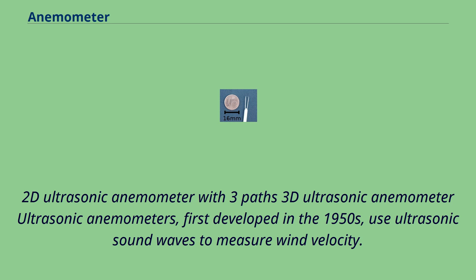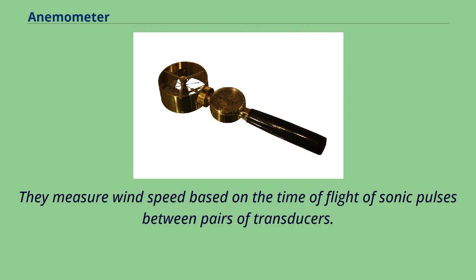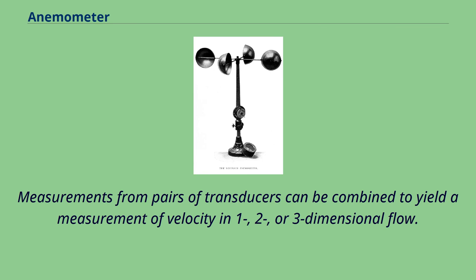2D ultrasonic anemometer with three paths. 3D ultrasonic anemometer. Ultrasonic anemometers, first developed in the 1950s, use ultrasonic sound waves to measure wind velocity. They measure wind speed based on the time of flight of sonic pulses between pairs of transducers. Measurements from pairs of transducers can be combined to yield a measurement of velocity in one, two, or three-dimensional flow.